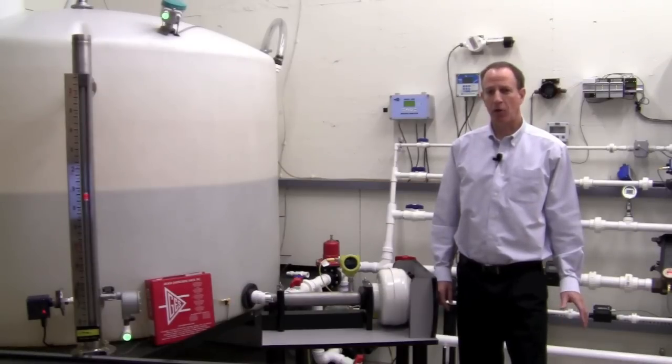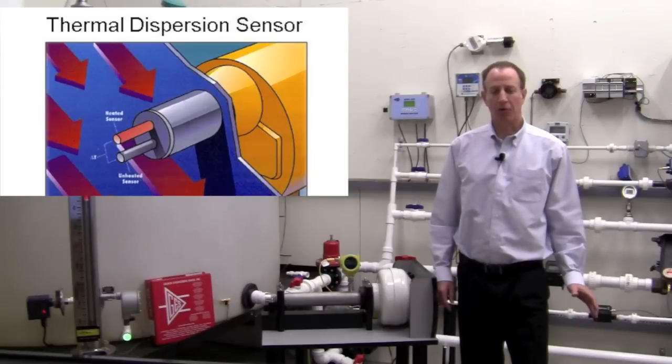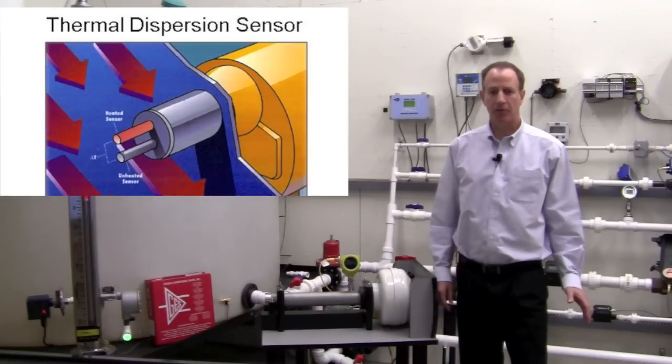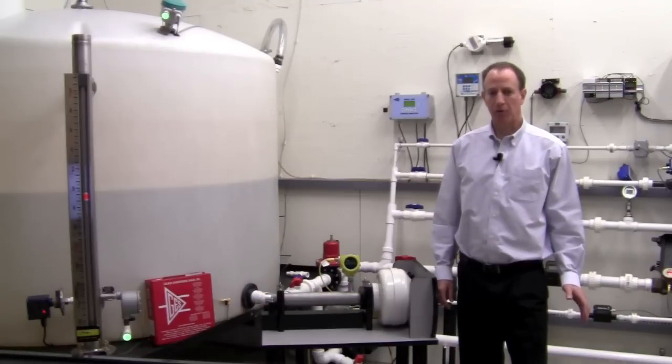The ST series of flow meters operates on the principle of thermal dispersion. The circuitry measures the temperature difference between the heated and non-heated sensors. The greater the mass flow rate, the less temperature difference between the two sensors.